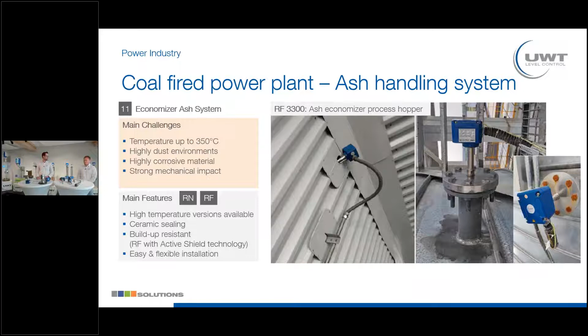You only have 4 steps to do the commissioning. You choose high level or low level. Then you set the time delay from covered to uncovered, or uncovered to covered, or on both sides. Then you set the time delay, and then you set the density, so the switching point, the picofarad switching point from uncovered to covered. So only 4 steps to commission the RF 3300, and it's a plug and play unit. That's also the reason why so many RF 3300 units are used here in the coal industry. Really simple to install and to commission.